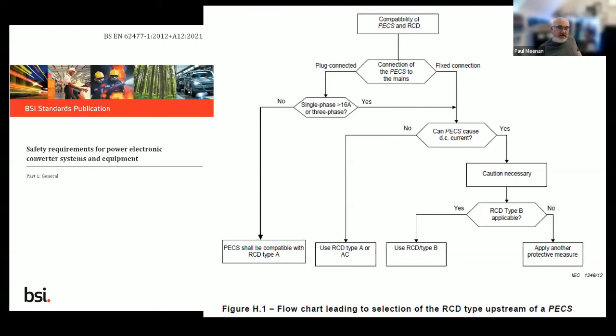But yet in our wiring regulations, we still have type AC, although it's strongly recommended that they're not used, and they have been banned around various parts of Europe. So it's really important you look at what your fixed installation will do. Is it a communications rack? Will it produce DC leakage from the switch mode power supplies? Of course it will.